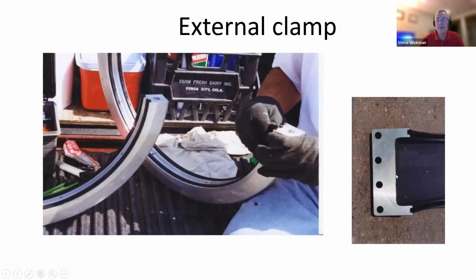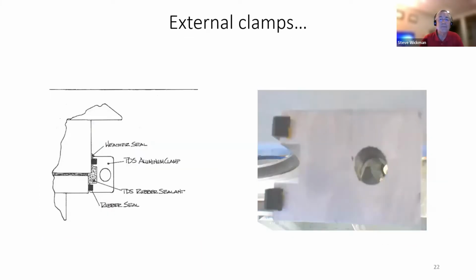In addition, this is just another style clamp over here to give you an idea that we can fabricate them in various and sundry sizes and shapes depending on the component we're going to enclose around. Graphic representation of what this looks like. Very common leak situation is this grout or gasket material that's between the porcelain and steel on a bushing that will develop leaks, fail, dry out, develop leaks. And this shows you how we would put the clamp around that bushing.